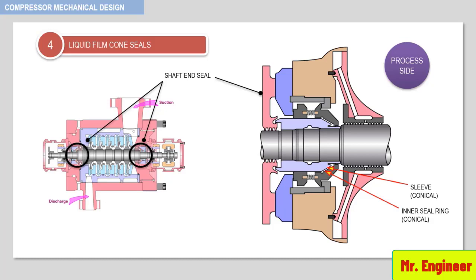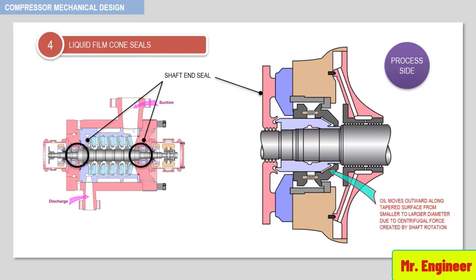When centrifugal force due to shaft rotation acts on the oil, the oil is forced to move outward along the sleeve and inner seal ring from the smaller to larger diameter. Thus, the amount of oil which contacts the process gas and gets contaminated is minimized.